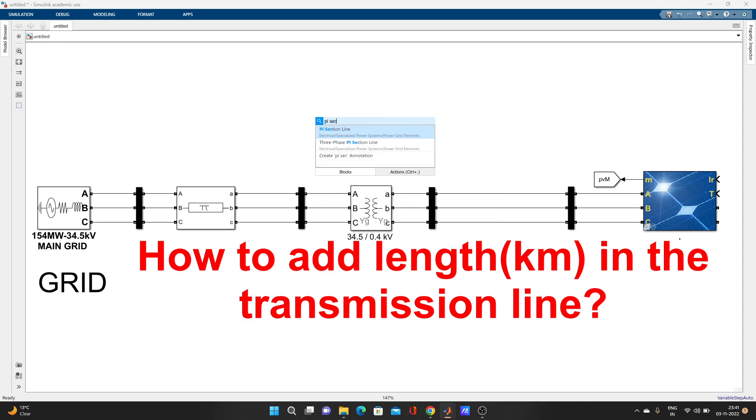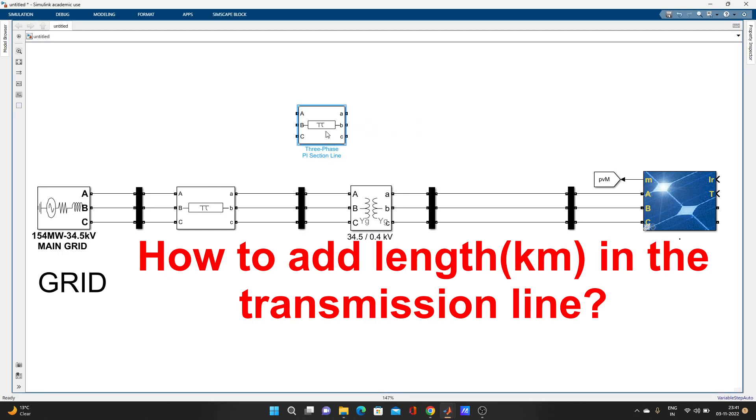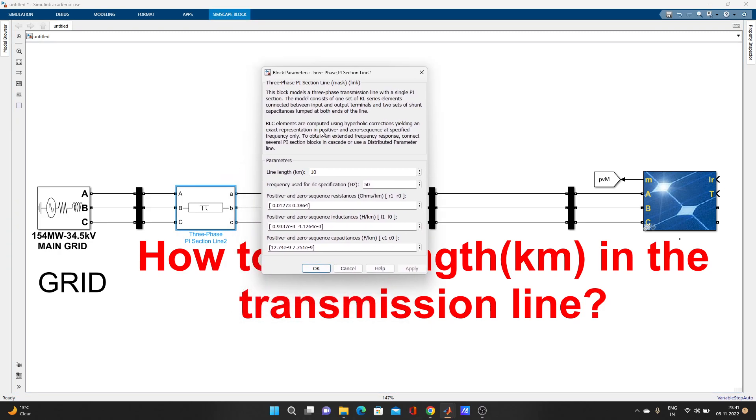Search PI section. It will come 3-phase PI section line. Look, the same thing I have added here. I will delete this one and now just double-click on it. So how to add that km? Just look here, it is line length in km. It is already there. You can give anything: 5, 6, 10, 1, 9, 100, whatever you need.